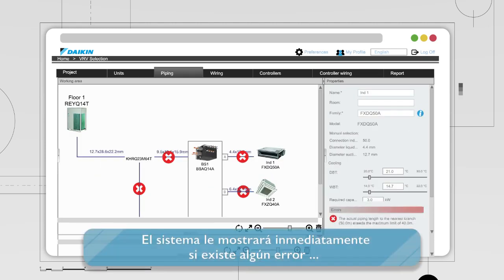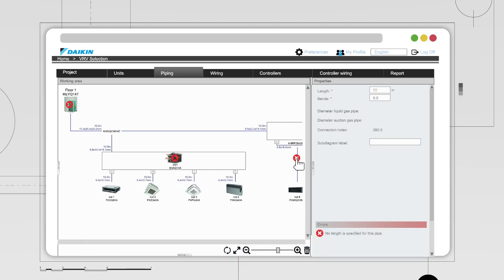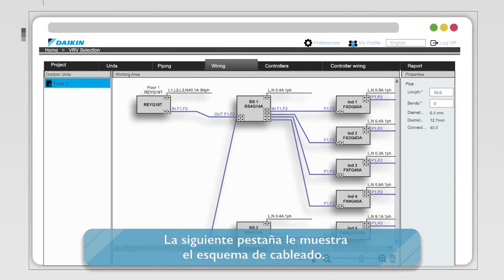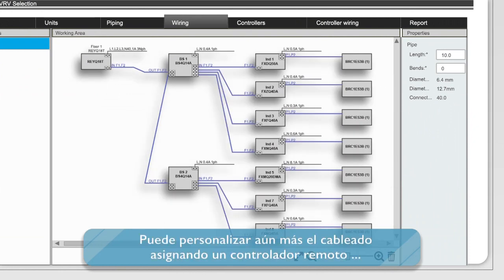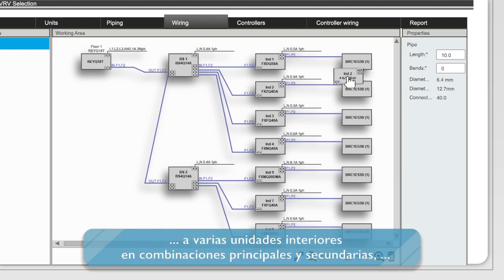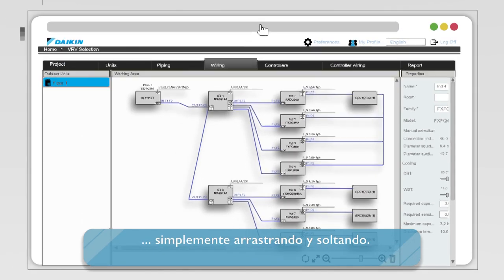The system will immediately indicate if any error exists in unit combinations or pipe lengths. The next tab brings you into the wiring schematic, where you can see both the power supply and control lines. You can further customize the wiring by assigning a remote controller to multiple indoor units in main and sub combinations, simply by drag and drop.